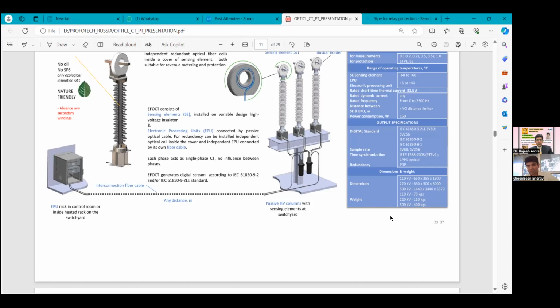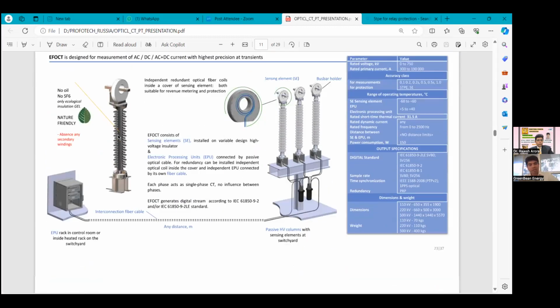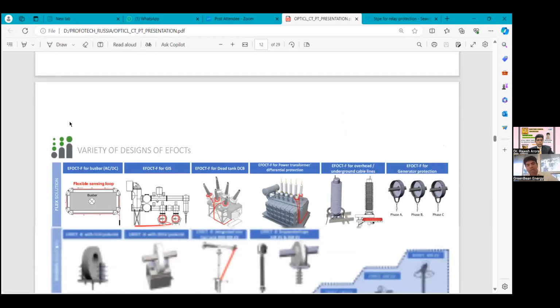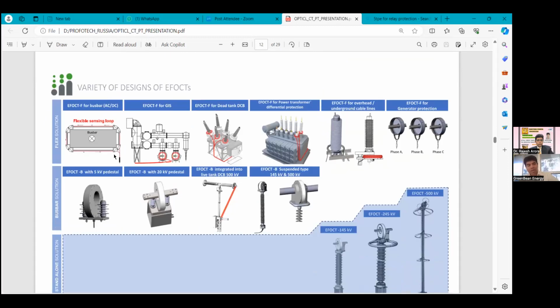Of EFOCT. The EFOCT for bus is useful for the processing industry, like aluminium furnace and chemical industry, where they are using a rectifier transformer and furnace duty transformers, where high currents are delivered to the equipment. Then EFOCT for GIS. This one is for GIS, where this is a flexible CT which can be installed on the GIS.